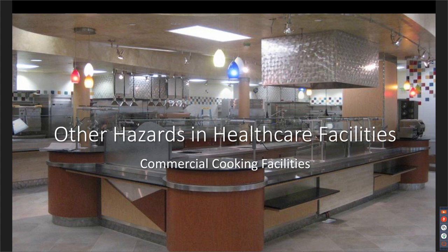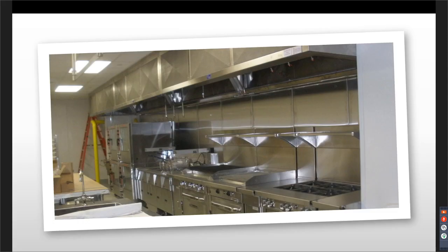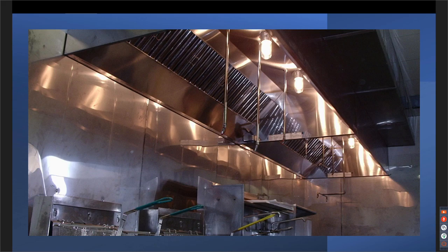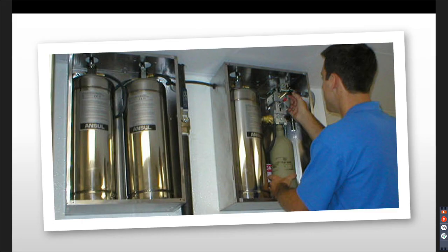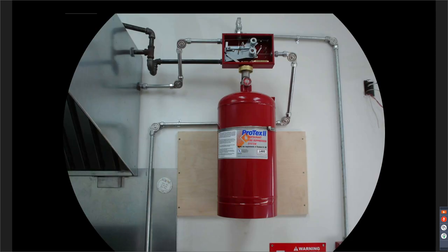If you have commercial cooking facilities in your clinic or in your facility, these have their own kinds of hazards. When we do a presentation of fires in healthcare facilities, fully 87% of fires that occur in healthcare facilities originate in cooking areas. And not surprisingly, we have combustible materials, we have grease-laden vapors that saturate or cover surfaces with a combustible kind of a film. We have special fire suppression systems that are designed to control these types of fires. Some of these systems are powdered in nature, some of them are liquid in nature.